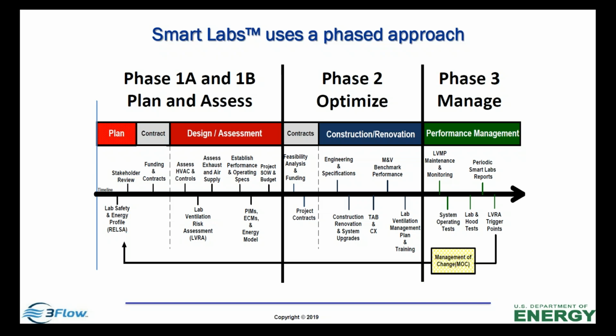So when I say challenge it, what we do is go in and open all the fume hoods, for instance, and see what the HVAC system is doing on both supply and exhaust. Then we close all the hoods and see what it does. We're basically defining the range of operation for the building itself. We take the risk assessment and put it together with the existing range of operation of the building, then see where that building fits or what it's doing. Often there's a lot of excess air, because buildings and labs have been designed that way.